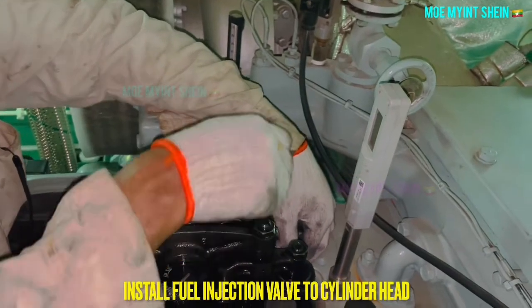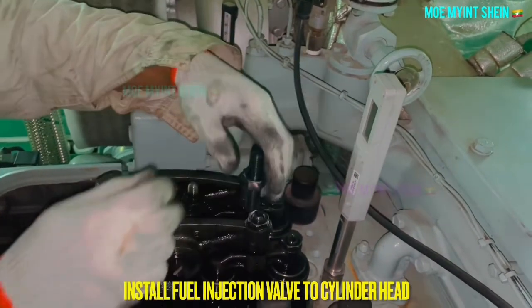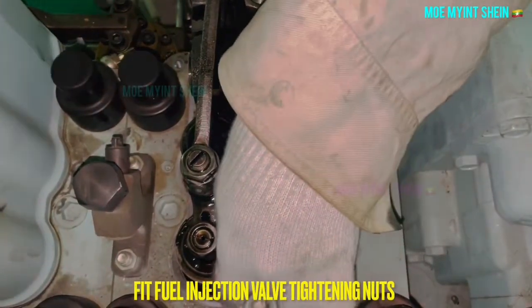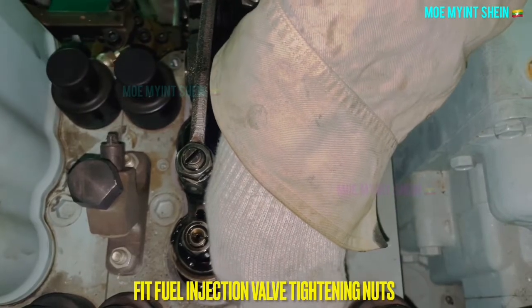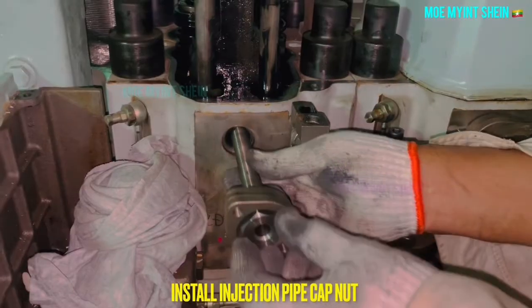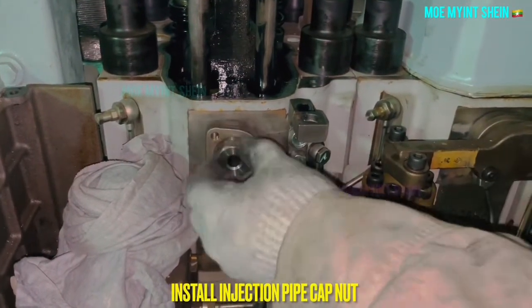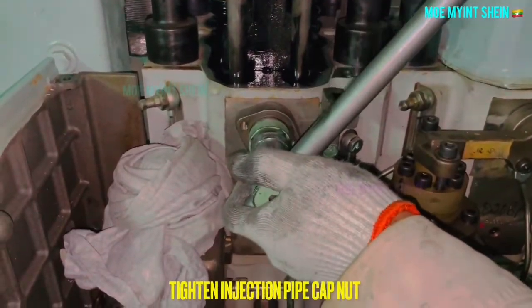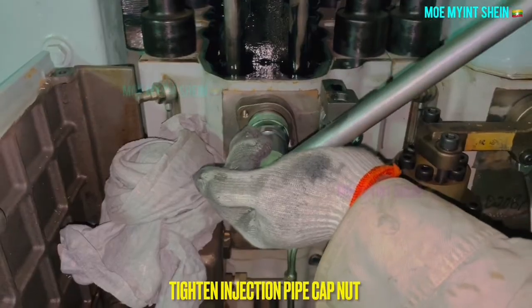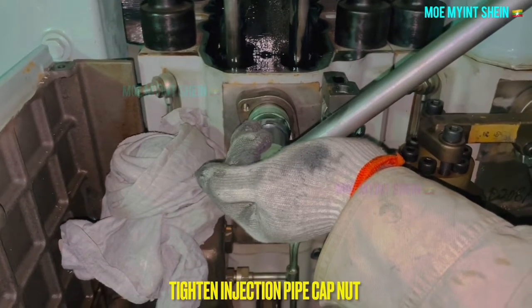After that, insert the fuel injector body into the cylinder cover. Fit the fuel injector tightening nuts. Install the injection pipe cap nut carefully — improper mounting of the cabinet can damage both threaded portions on the pipe and the injector body. Tighten the injection pipe cap nut.